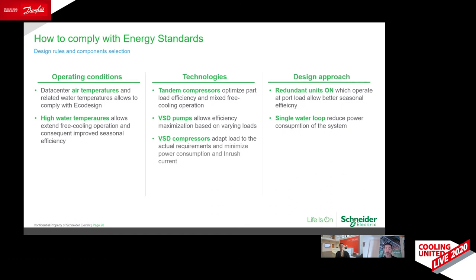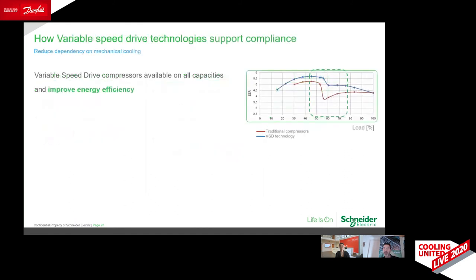If you select variable speed drive compressors, pumps, or other logics for the compressor, the efficiency is much higher. So it is our choice to design with that. It is your choice to select the unit designed for that. Certainly there are tools right now to comply with this, and we need to work together to make it happen. In particular, when you look at variable speed drive compressors, part load conditions are much more efficient.